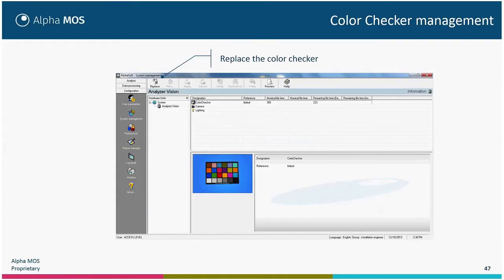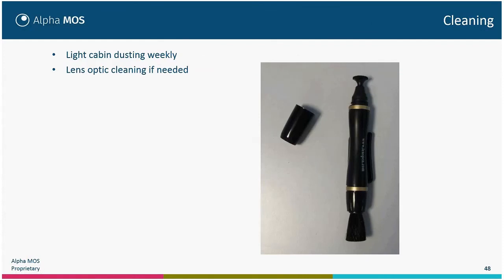Now we will talk about maintenance, which is quite simple. The color checker should be replaced every year. When you receive a new color checker, click Replace and enter the date of replacement. The light cabin should be dusted every week — you can use water and a paper towel. Never use organic solvent. If the lens optic is dirty, you should use the cleaning pen specifically designed to avoid scratches on the optics.